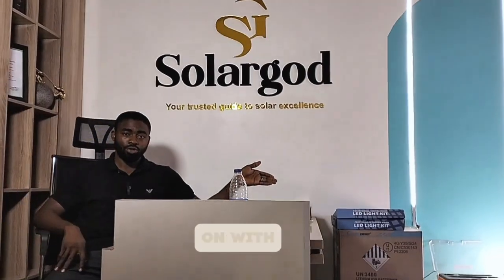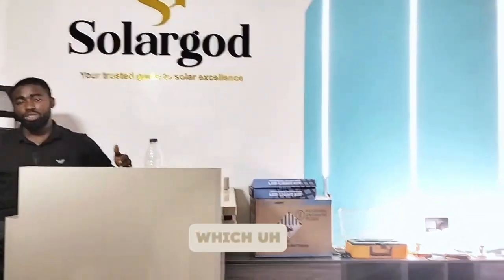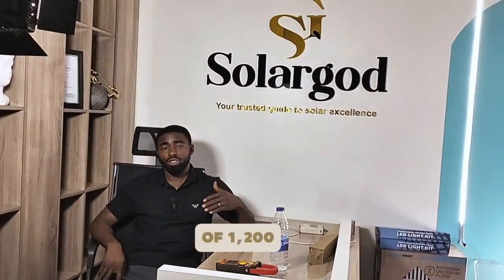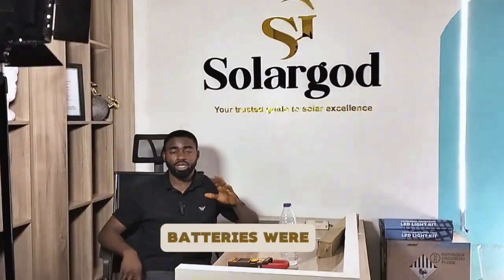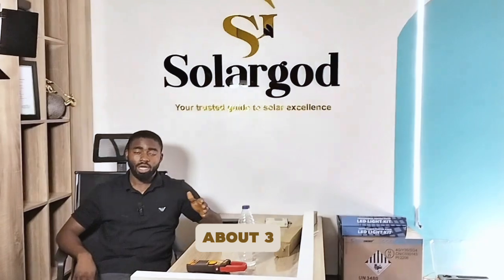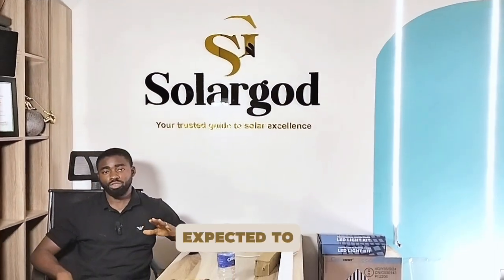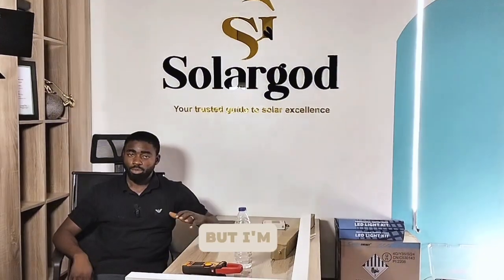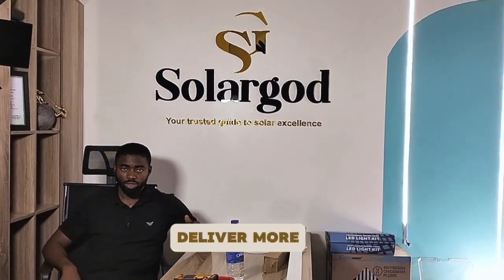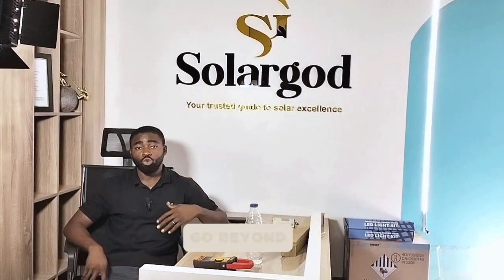The system is still on with the same amount of load, which we are draining about 5.1 amps from the inverter, a total of 1200 watts, and the batteries were able to endure for about 3 hours plus. So on the norm, the battery is 80% DOD, which is expected to deliver 3 hours 30 minutes, but I'm 100% sure that the battery will deliver more than that. So the battery has proven that it can go beyond that.